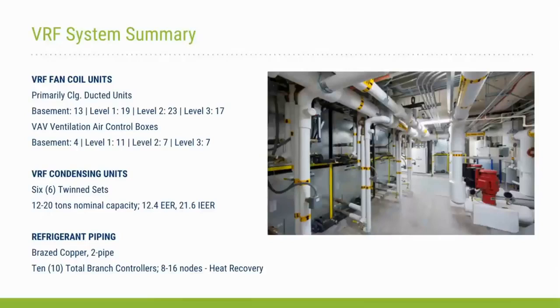We ended up choosing a water source VRF system. This was a measure in order to drive the energy use intensity target achievable down further, in order to balance with the limitations to how much on-site renewable energy could be provided for the net zero energy goal of this project. We ended up with 6 twin sets of water source condensing units. You can see these installed on the left side of the picture on the screen, and each set had between 12 to 20 tons of nominal capacity.